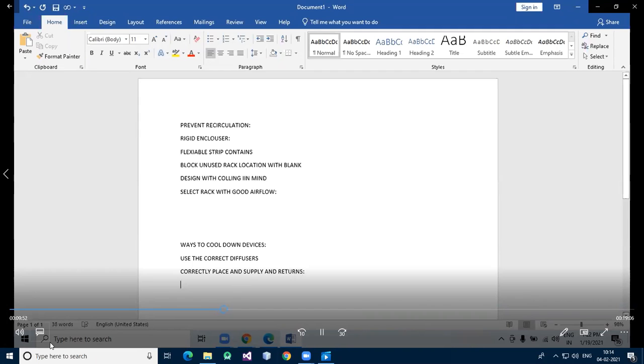Diffusers should be placed right by the equipment to be cooled. They should not be placed so they direct cooling air at the heat exhaust, but rather into the air intake. Supplies and slotted floor tiles should not be placed near returns, to prevent cool air short circuits. Minimize air leaks. Systems that use a raised floor can lose cool air through cable access in hot aisles. Optimize air conditioner placement.